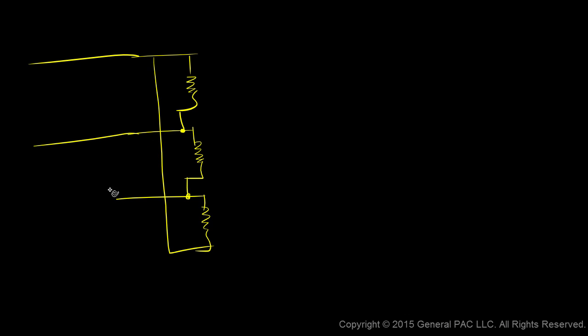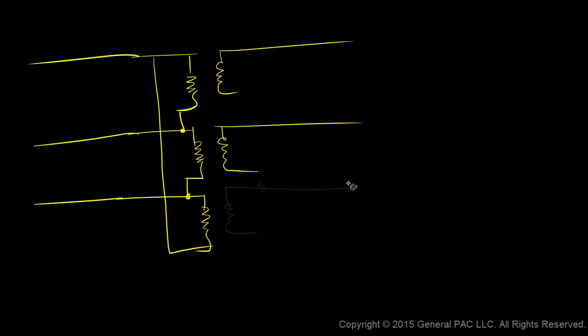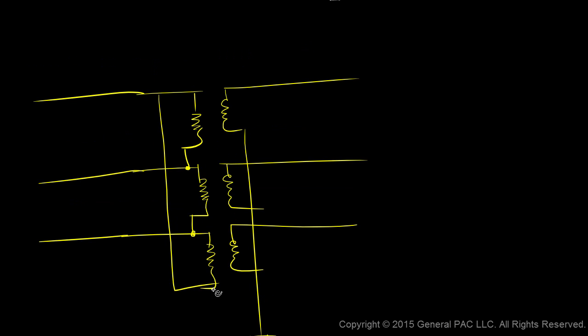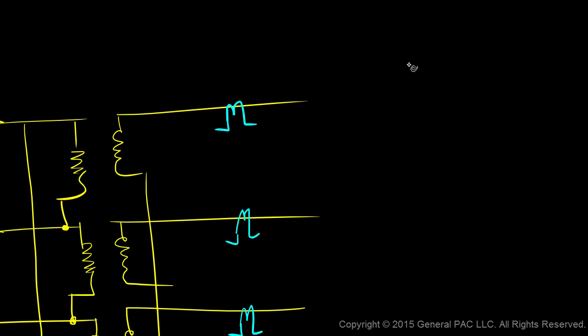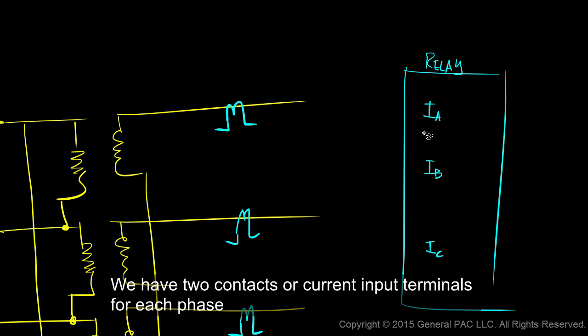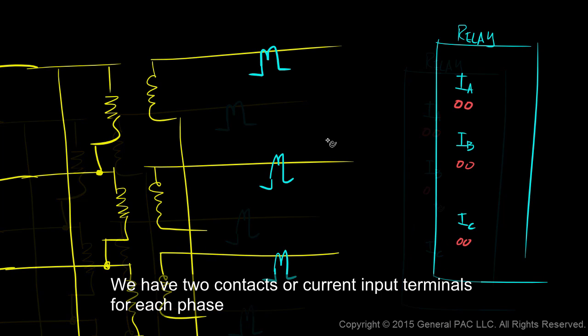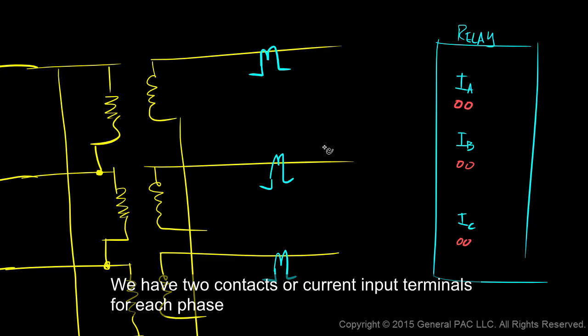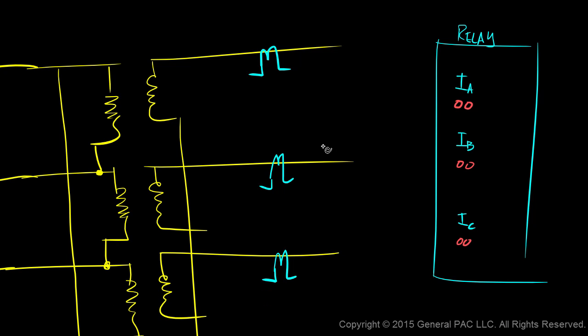Let's begin by drawing a delta-connected transformer. This is line A, this is line B, and this is line C. On the secondary side, suppose we had a Y-connected transformer that was grounded. On this Y-connected secondary side, we have CTs connected on each phase. Let's suppose there is a relay that we want this CT to connect to. On this relay, we have inputs for IA, IB, and IC, and we have two contacts for each phase.